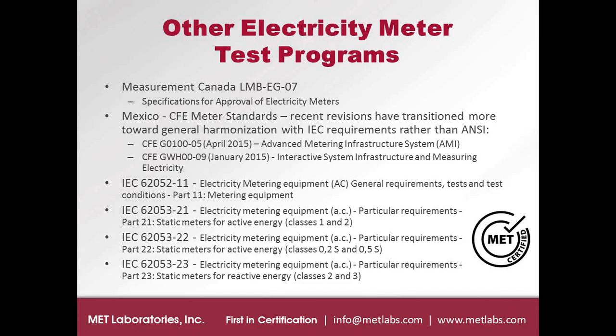We also test quite a bit of meters that are going to be sold in Mexico under the CFE standards. And what we're seeing there, where traditionally those standards in the past have been very much like the ANSI C12 standard, there's been some changes where they're really harmonizing a bit more with the IEC type testing, where I like to say it's sort of the same. You're looking for the same things, but they go about it a bit different, and there's different test points and so some different types of tests that are run as well. So we're seeing the Mexican standards really evolve toward harmonization more so with the IEC standards and not so much with the ANSI any longer. And then there's the group of the IEC tests that we also offer in terms of test programs for more global, international compliance.